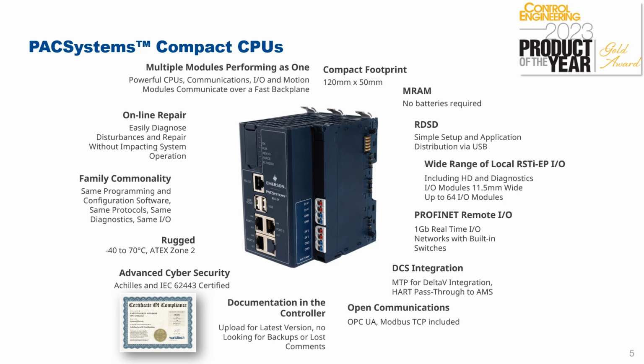We have very good online repair with diagnostics and the ability to replace modules without powering down the system. These units are particularly rugged with -40 to +70 degrees C temperature rating and ATEX Zone 2 support. We have very good cybersecurity with Achilles and IEC 62443 certification. The units themselves support simple backup and restore of applications and a wide range of I/O, including local RSTi-EP I/O, as well as distributed I/O using Profinet with a built-in Profinet controller and network switch.